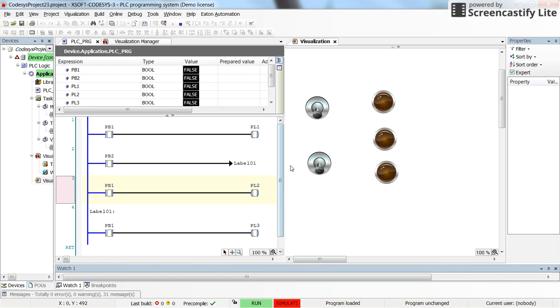Here, PB2 is determined by this switch, and push button 1 by this one. You can see here that as long as PB2 is not turned on, the PB2 contact is not true, we don't see the effect of the jump to the label. By turning PB1 on and off, all three pilot lamps are turned on or off.